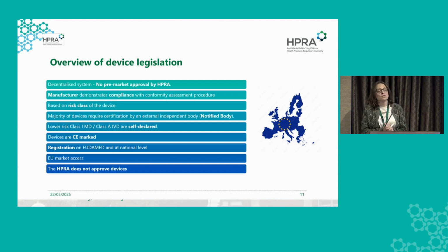Really, the onus is on the manufacturer to demonstrate compliance with the regulatory requirements and to follow a conformity assessment procedure based on the relevant risk class for the types of devices they manufacture. The 4 risk classes range from the lowest risk, class 1, and for devices they go from class 1, 2A, 2B and 3, based on the level of invasiveness in the body and the duration of time that they're in contact with the body.